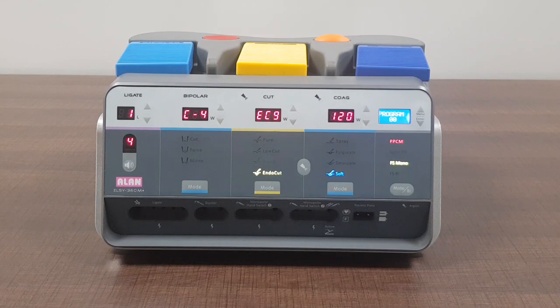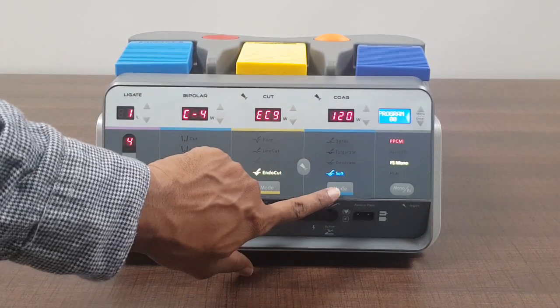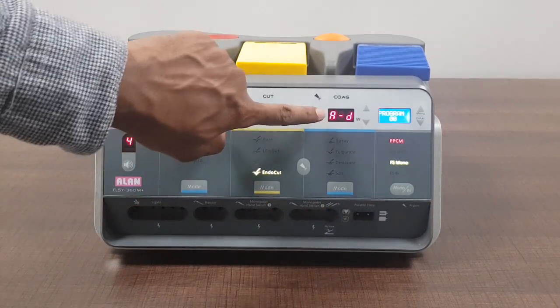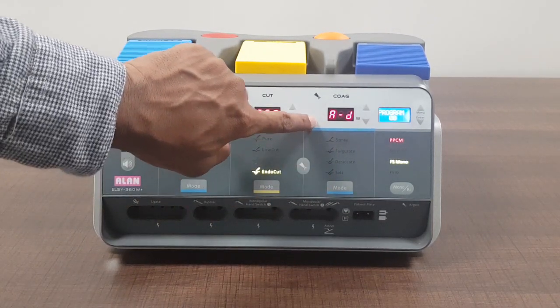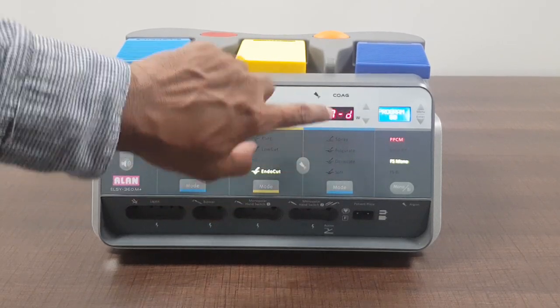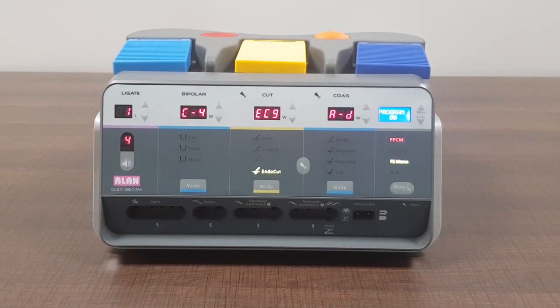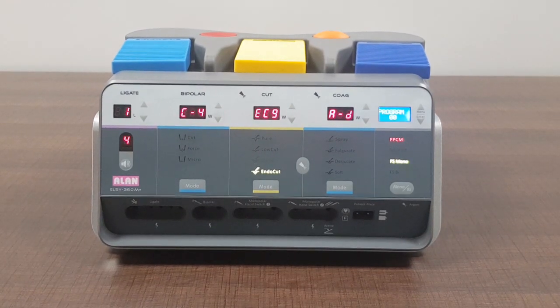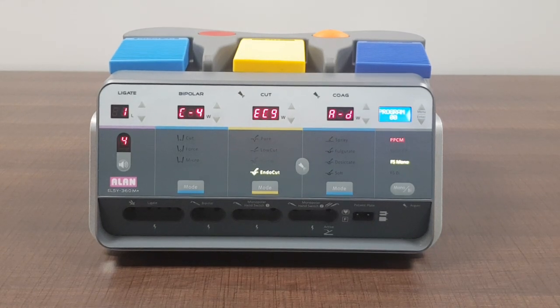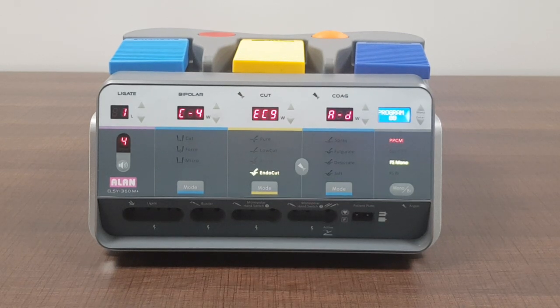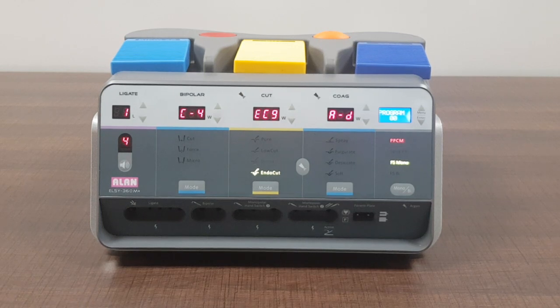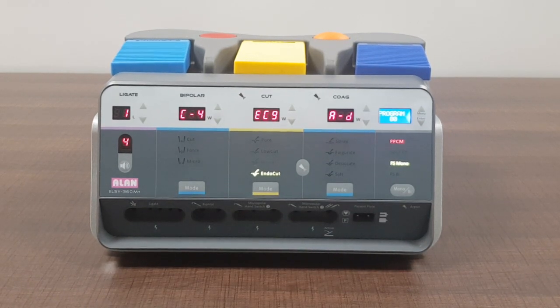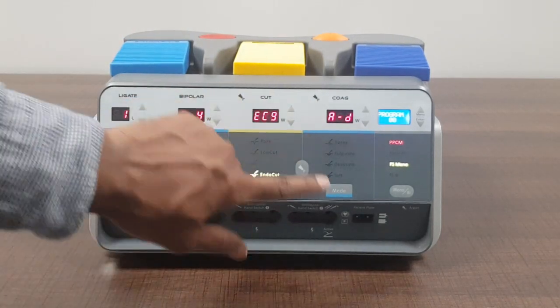Now the next is, it shows us AD although nothing has been highlighted, but AD means auto desiccate, which means it is a form of desiccation. But here the machine senses the coagulation, which means in previous four modes whenever you coagulate the control is in your hand when to stop and when to start. But here once you start it will stop automatically. You don't have to stop it because it senses the resistance and according to the resistance it will stop because the machine would be the best judge here. And if you feel like the doctor is not able to identify then I would say auto desiccate is good.